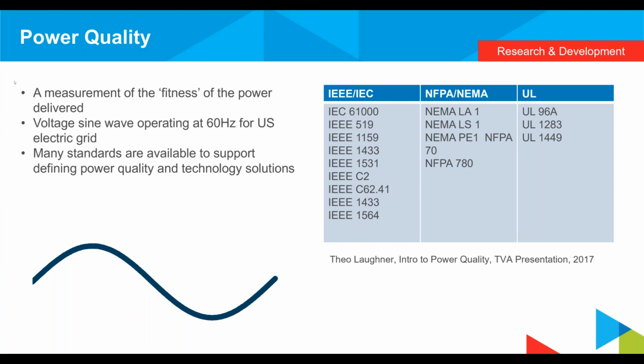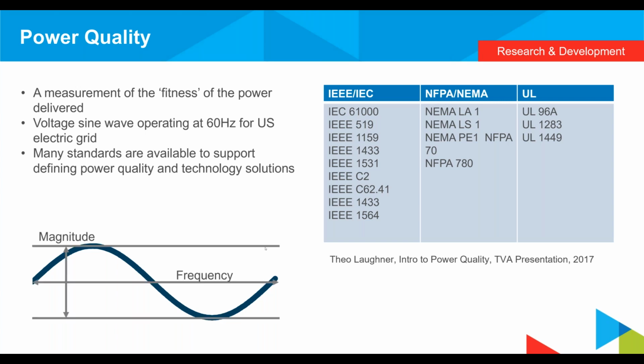In this case, what is power quality? It's essentially a measurement of the fitness of power delivered. And it's typically a voltage sine wave operating at 60 hertz for the US electric grid. In other countries, it could be 50 hertz, but in this case, it's 60 hertz. There are many standards available to define the power quality: IEEE standards, IEC, National Fire Protection Association, NFPA, NEMA, and UL. Overall, when we talk about power quality, the magnitude of the voltage has to be regulated within a certain tolerance, and the frequency of the voltage has to be regulated within a certain tolerance.